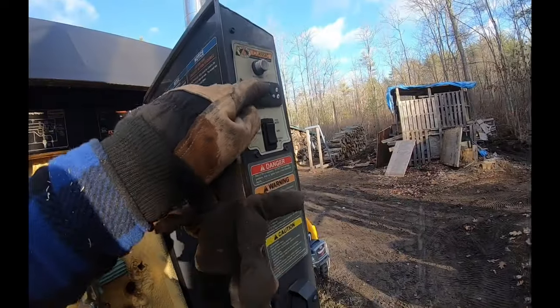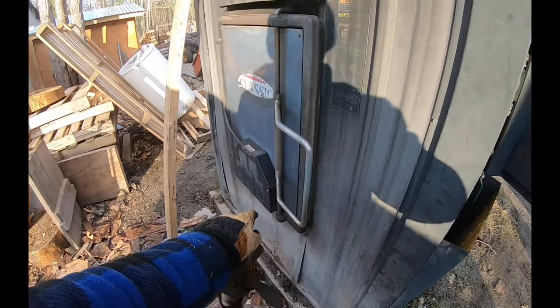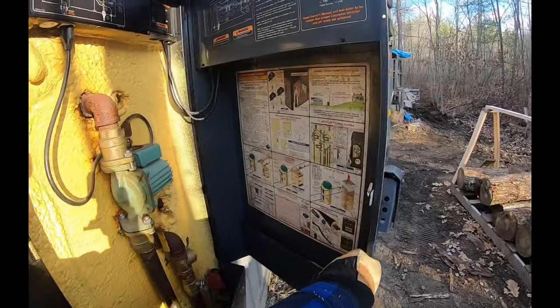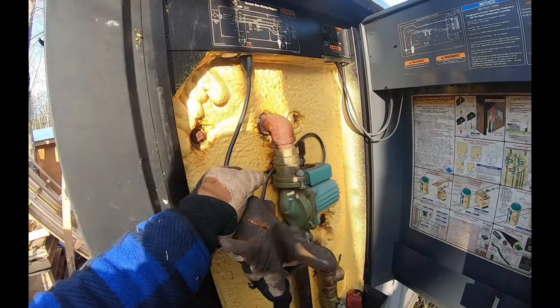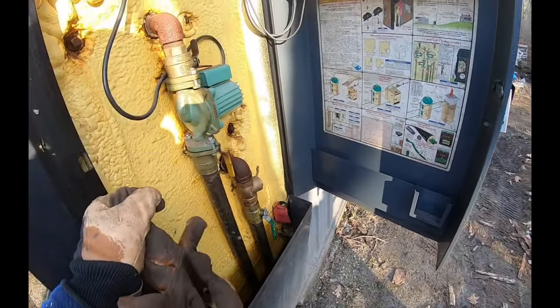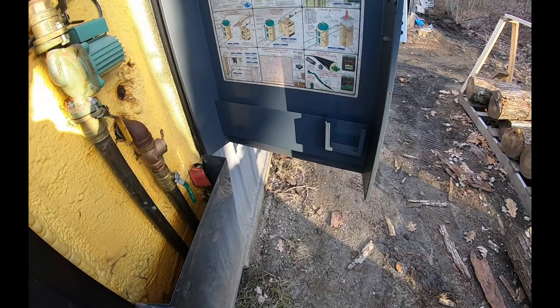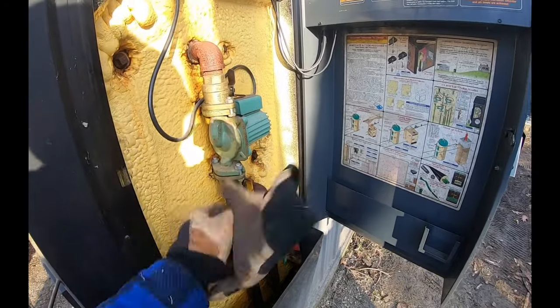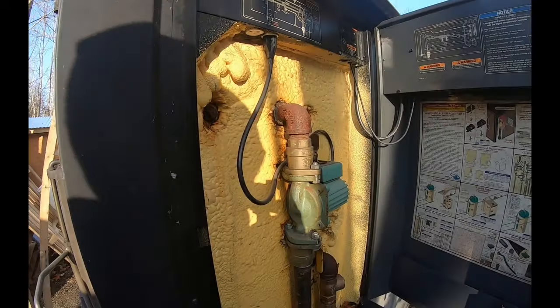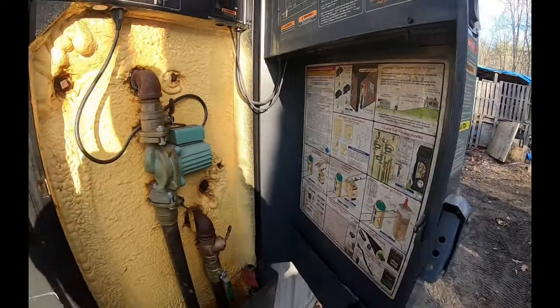As far as telling what temperature your machine is at, you're kind of up the creek — you won't be able to tell. The only way to restore power to the temp sensor and the damper is getting your generator up to speed on the full panel. The only thing you can do separately is take this plug out and plug it into a small Honda generator or similar, to at least still circulate the water and buy yourself however many hours of fighting chance to get main power back on.